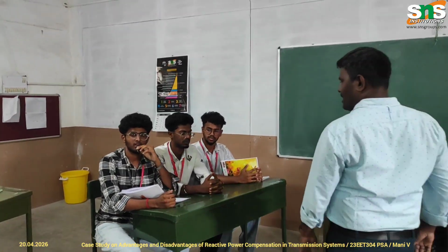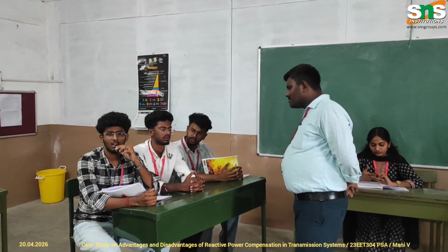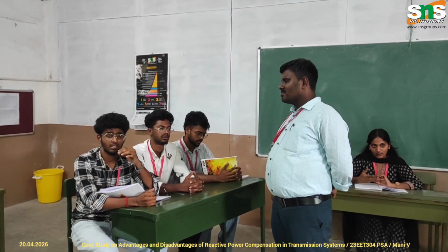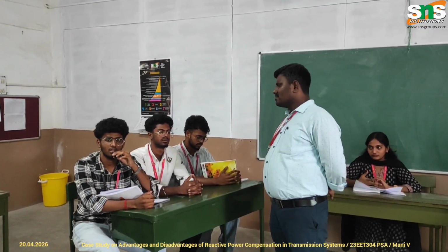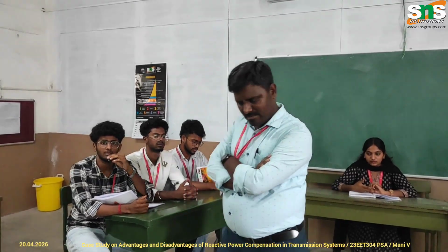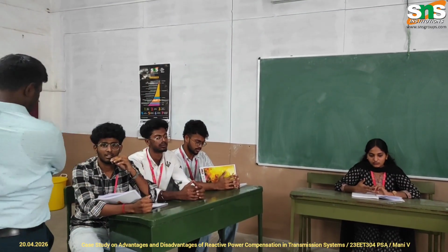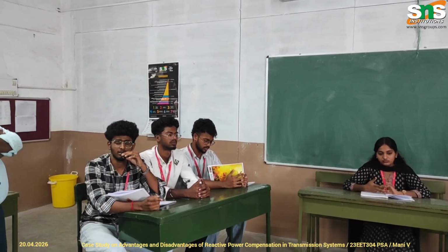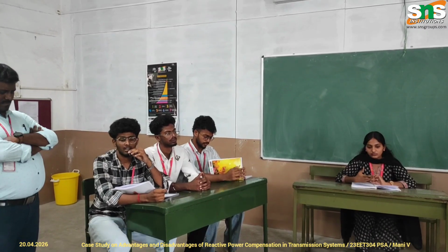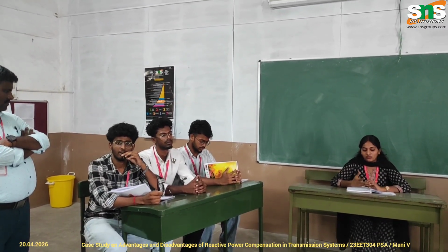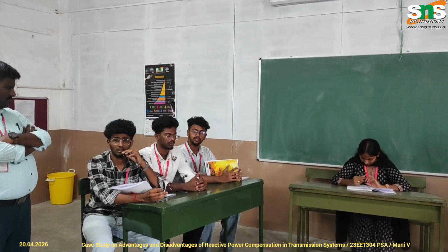I am going to discuss transmission efficiency and losses. First, about the advantages: the reduction of I squared R losses. The compensation improves the power factor, which reduces the current that passes through the line for the same real power, and a higher level of current leads to a higher level of heat losses.